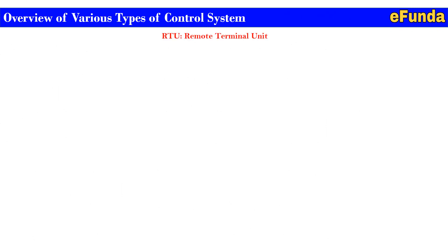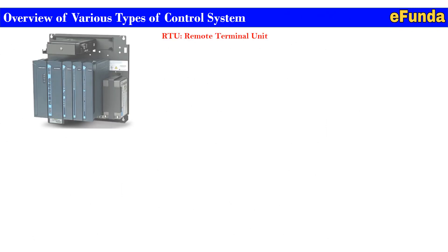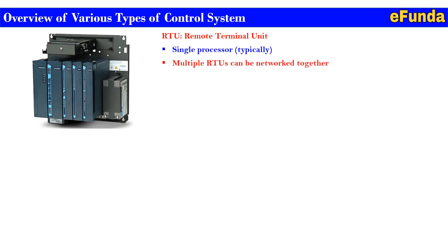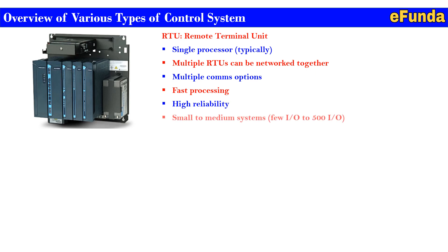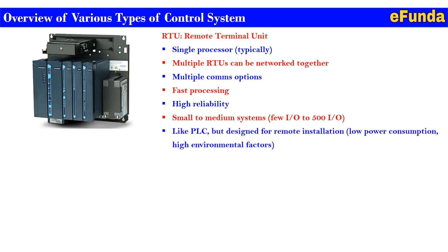RTU, Remote Terminal Unit. One can refer to the picture showing the structure of an RTU unit, which consists of a single processor typically. Multiple RTUs can be networked together with multiple communication options, fast processing, and high reliability. It is a small to medium system with a few IOs to 500 IOs, similar to PLC but designed for remote installation with low power consumption and tolerance to high environmental factors.